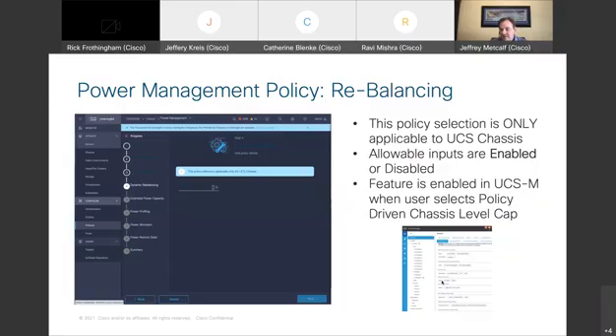This is rebalancing, which we already have today. Within the chassis you have a certain amount of available power, but not all workers consume their full power allocation simultaneously. So we try to minimize stranded capacity with static loads. Each endpoint is given an initial budget. If that node is consuming 90% or more of its allocated budget, it makes a request to increase its budget. The chassis management controller looks across all endpoints, and if one is consuming less than 75% of its budget, it redistributes that power allocation from the low consumer to the high consumer. This ensures stewardship of all available power, avoiding stranded capacity. This policy was enabled and always on by default within UCSM.